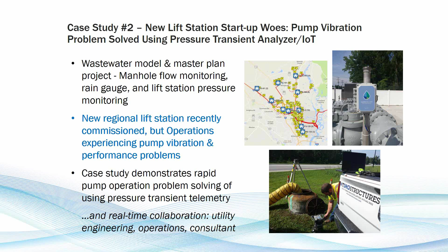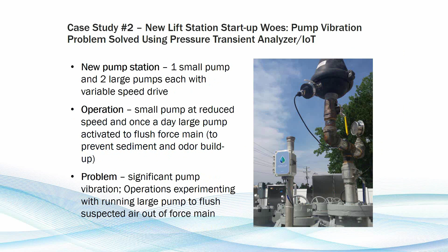So this case study demonstrates how deploying the right IoT device, during a larger field monitoring program, instantly paid for itself just to help address this chronic pump problem. So this pump station consists of one small pump and two large pumps, each with variable speed drives. So operations was running the small pump at reduced speed, and oftentimes when new lift stations are brought online, they're obviously designed for future conditions, so flows are a little low, and so they're running this first small pump at very low speeds and low pressures, and then once a day running the large pump to flush things out. However, the pump operation was getting a lot of vibration on both pumps, and they were having issues they couldn't quite resolve.